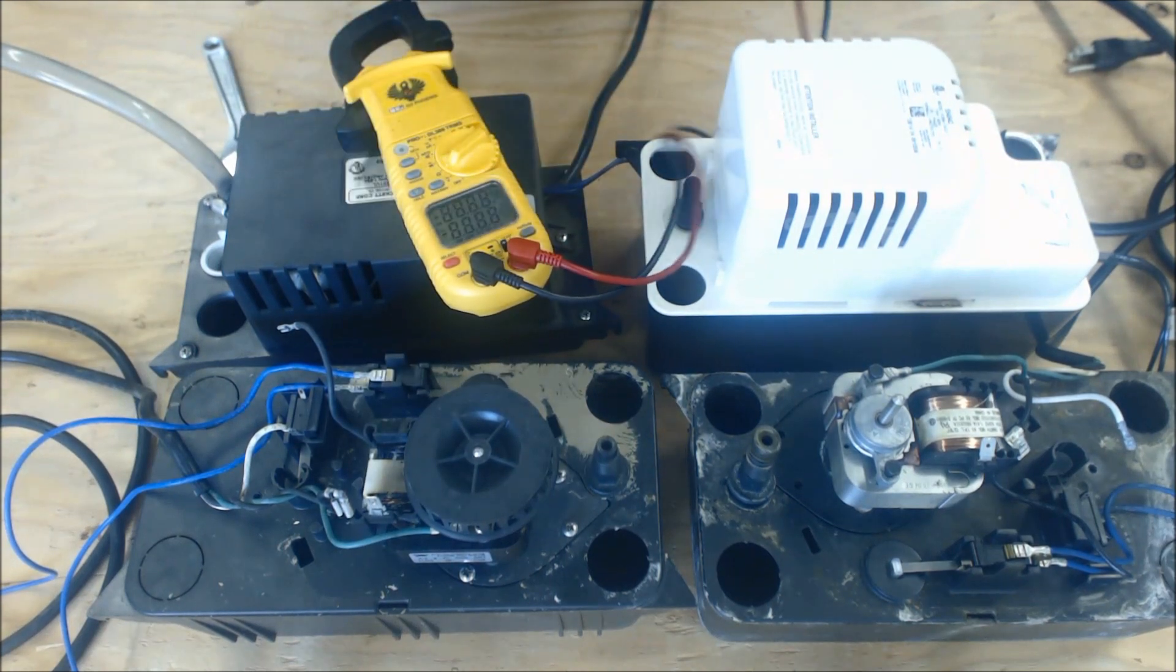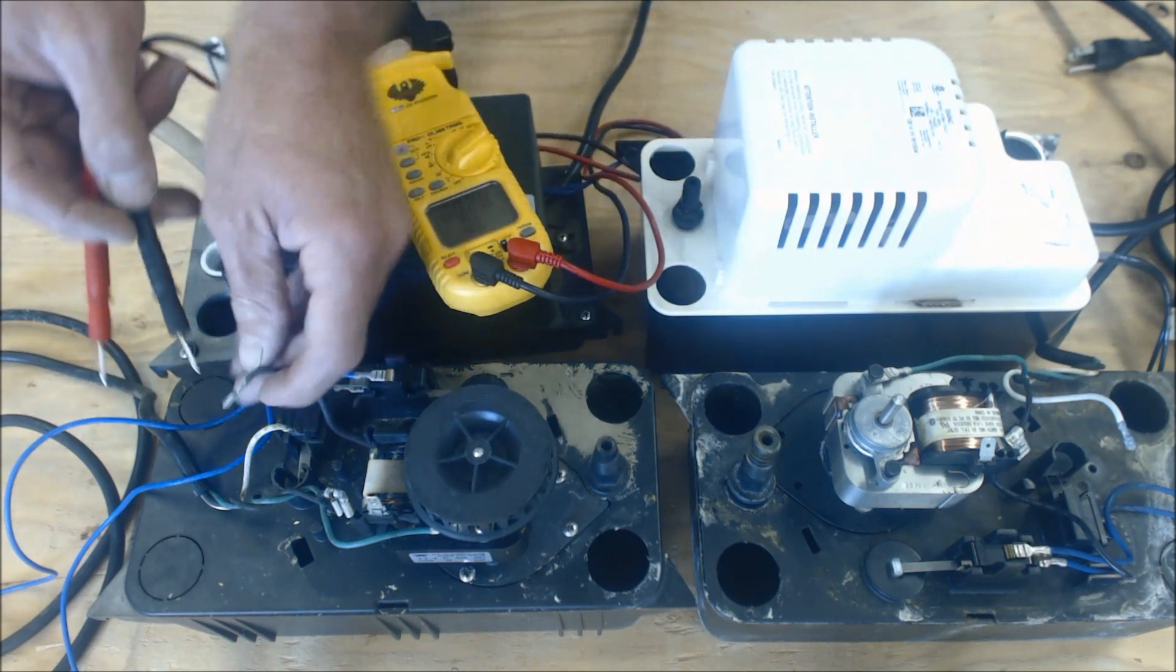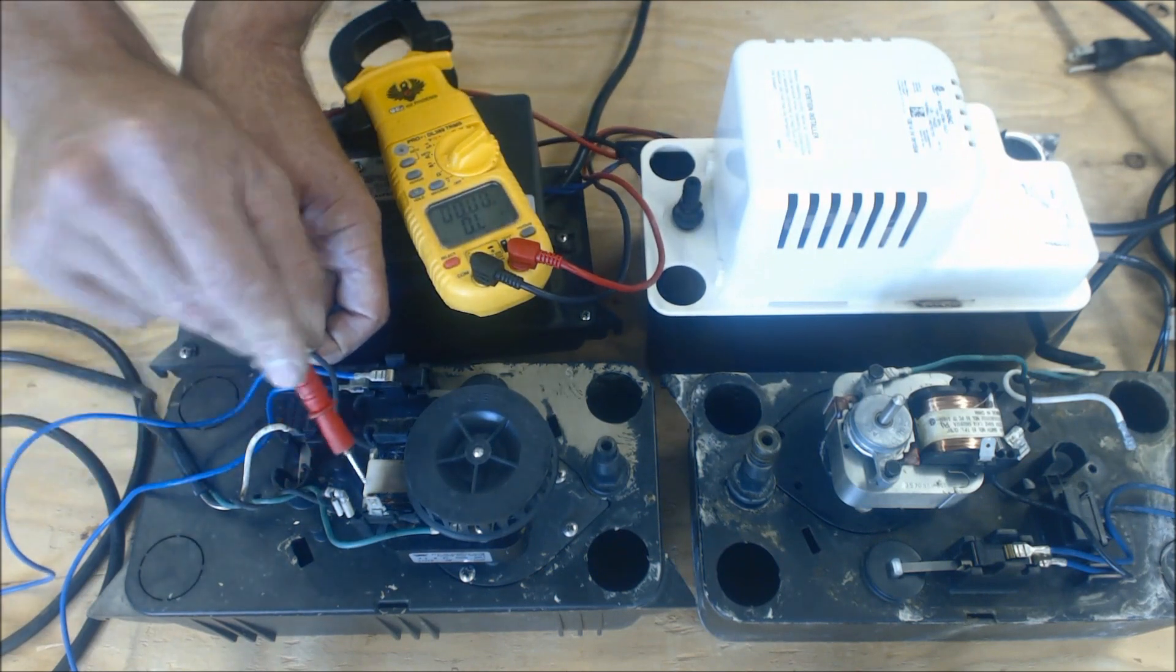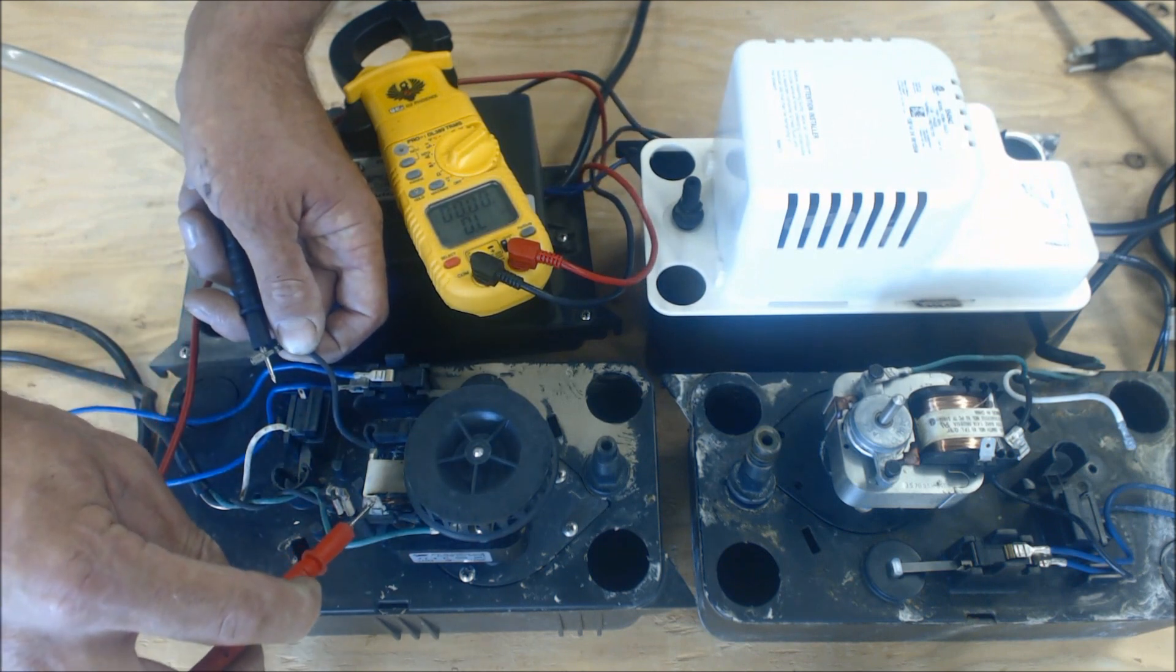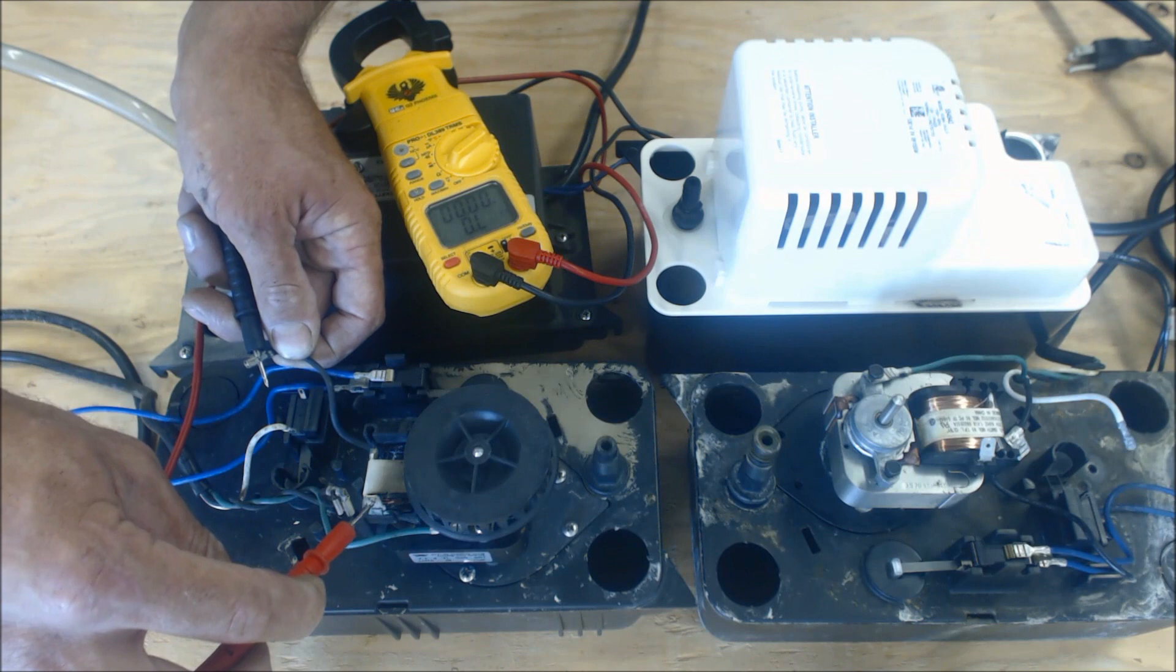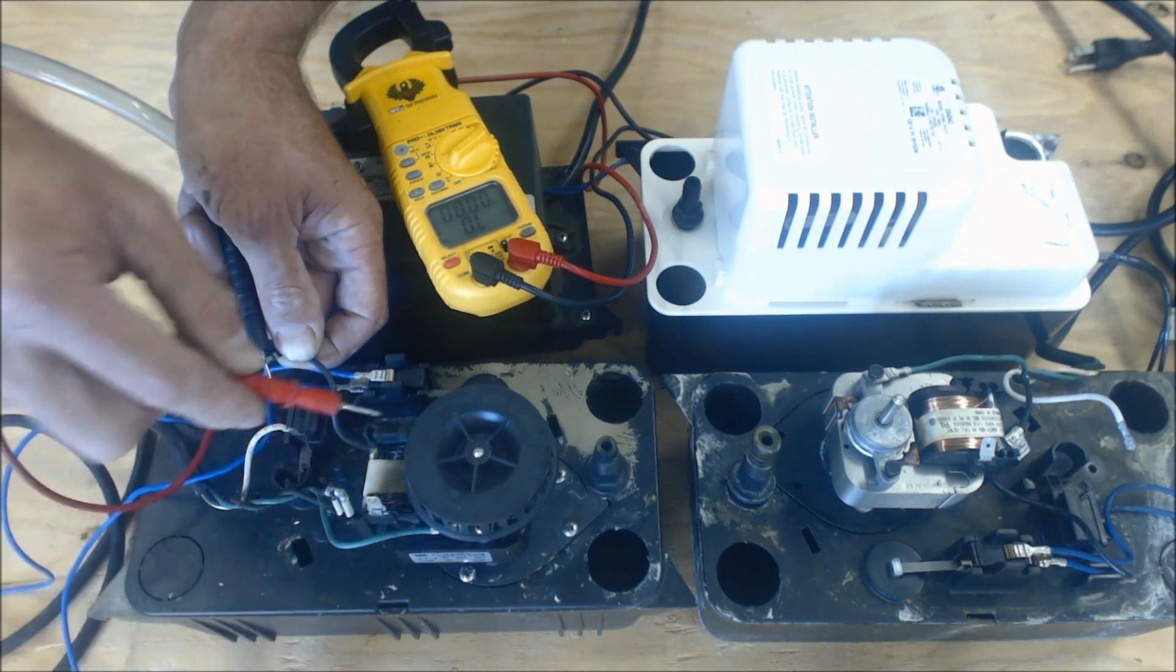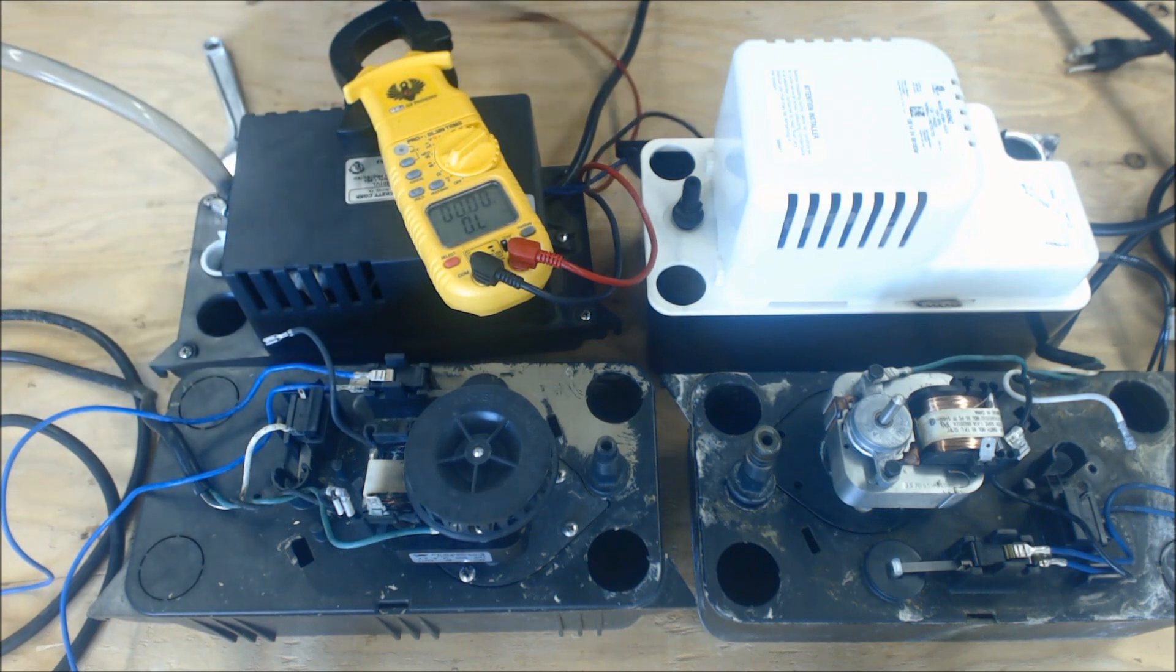We're going to turn our multimeter onto resistance, and we have OL. So it's over limit, that means that the windings are actually burned apart.